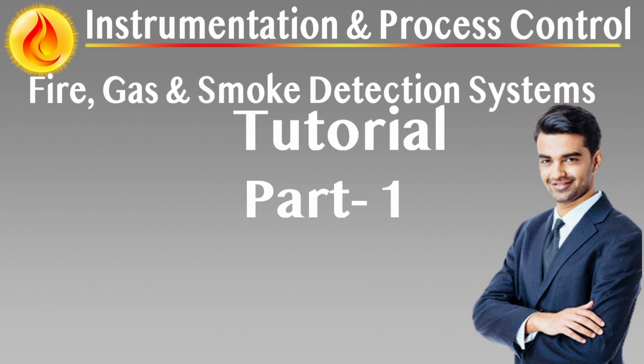Poisoning susceptibility, sensitive to H2S, silicones, halogens, and lead compounds, which reduce sensor life and accuracy. Slow response. Typical T90 response time is 20 to 30 seconds, compromising early detection and fast dispersing releases. High maintenance. Frequent recalibration needed due to drift caused by temperature changes and sensor aging.